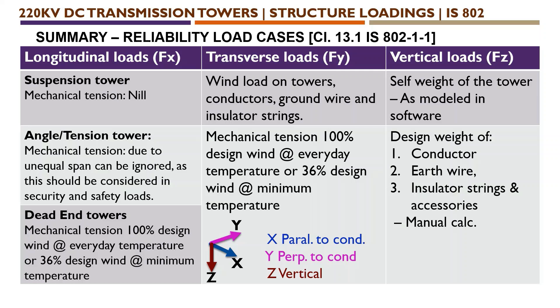For vertical loads, we need to consider the self weight of the tower as modeled in the software, because the self weight of the tower is given in the model itself by selecting the self weight option. In addition, we give the weight of conductor, earth wire, insulator strings and accessories, which we calculate manually. These are the three directions X, Y, Z — where X is parallel to the conductor span, Y is perpendicular to conductor span, and Z is vertical downward.